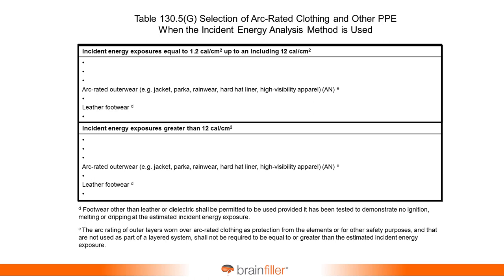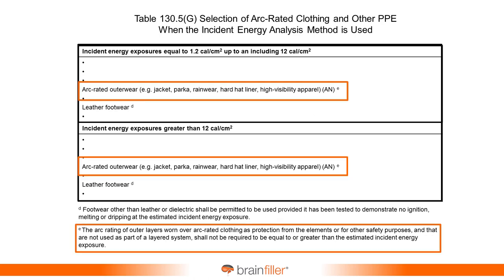And so now for the arc-rated outerwear or high visibility apparel, they used to have the word safety in there, that was removed. Down at the bottom, that's where you're going to find the note about the arc rating of the outer layer worn over the arc-rated clothing as protection from the elements or for other safety purposes, and that are not used as part of a layered system, shall not be required to be equal to or greater than the estimated incident energy exposure.